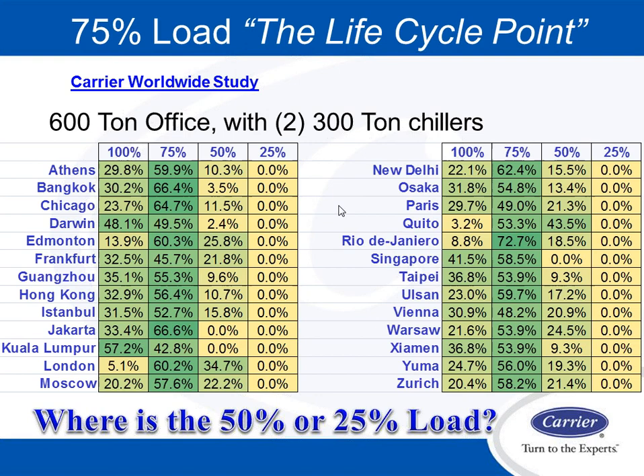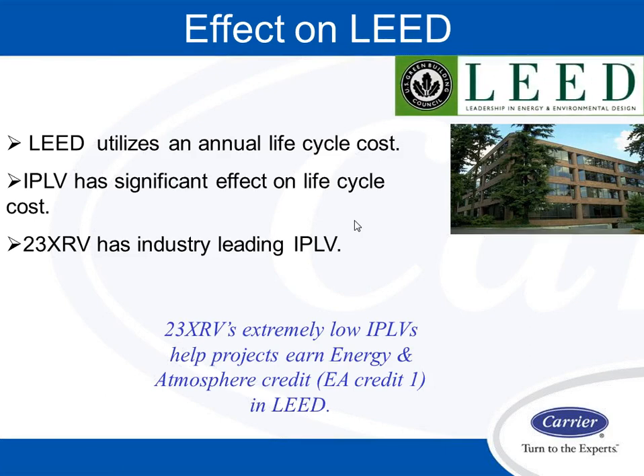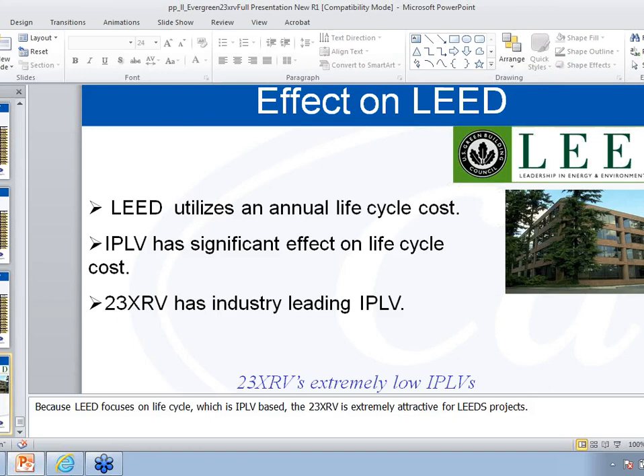Let's look at a 600-ton office with two 300-ton machines, and we see that an awful lot of times also, where in Chicago, and we analyzed all different cities throughout the world, we had Chicago 23% at 100%, 75% is 64.7, and the 50% load point happens 11.5, but the 25% load point never happens. Okay, so again, when we talk about the 23XRV, it has a very big impact on LEED. You have to analyze IPLV. Let me just go back to the original slide.